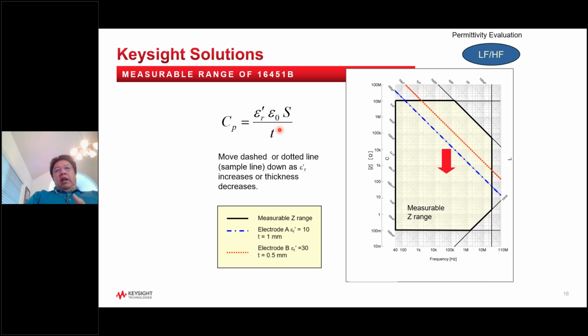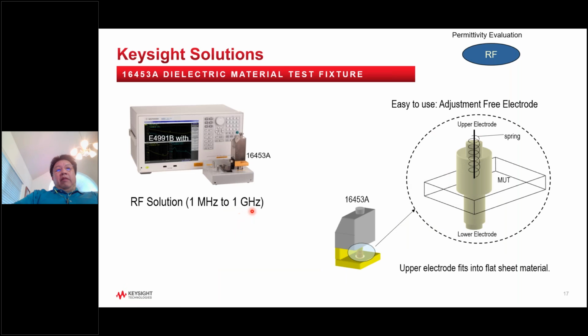Because we are using the impedance analyzer, we have to make sure that the measurement range is within the measurement capability. This graph shows that the black solid line is the measurement zone. This example shows that the blue dotted trace is Dk of 10 and thickness of 1 millimeter. When thickness is increased, this could affect your measurement zone. In that case, perhaps you have to trim or change your thickness to be thinner, so that you move your measurement zone down to the center of the measurement zone area and make the measurement more accurate. Okay. So this solution goes up to 1 gigahertz.